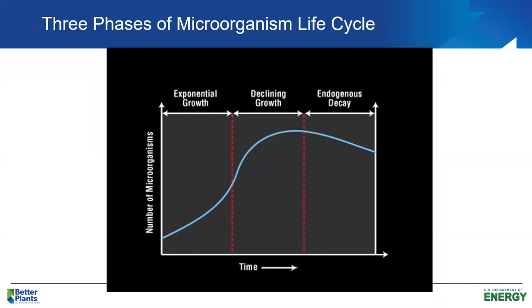Looking at the phases of growth in biological treatment: if we took a beaker of influent wastewater, added sludge, and measured microorganism concentration over time, we'd get a growth curve represented by the blue curve in the diagram. Initially, microorganisms acclimate to their environment, then we enter the exponential growth phase — plenty of food, bacteria reproducing rapidly. We typically don't operate activated sludge in the exponential growth phase because we get poor settling sludge and too much organic matter in the system and effluent.